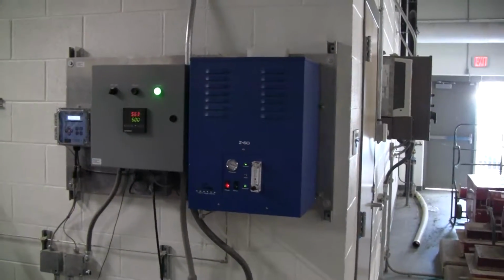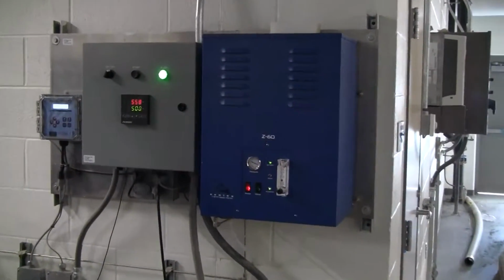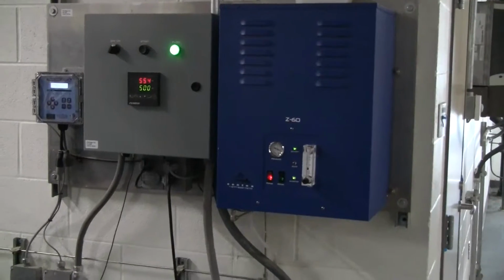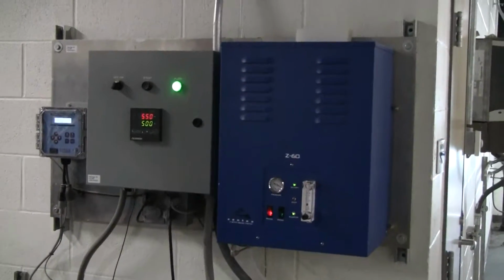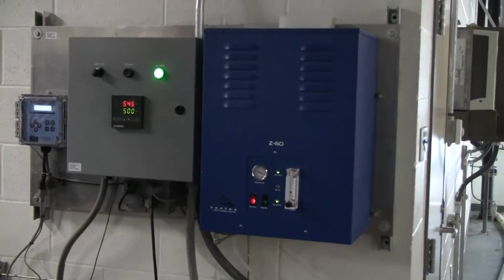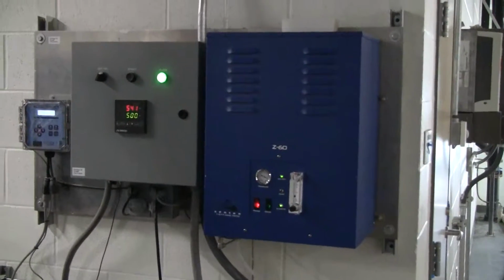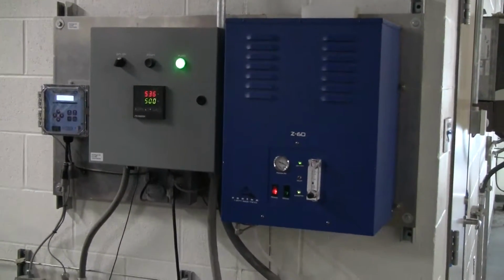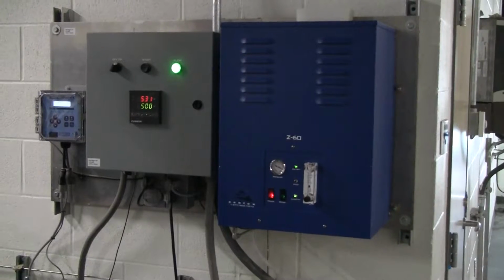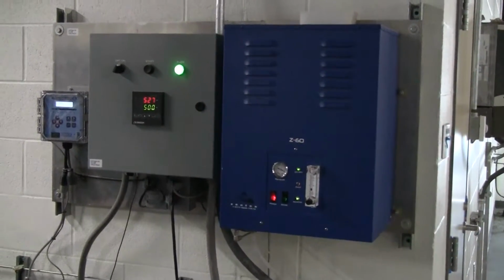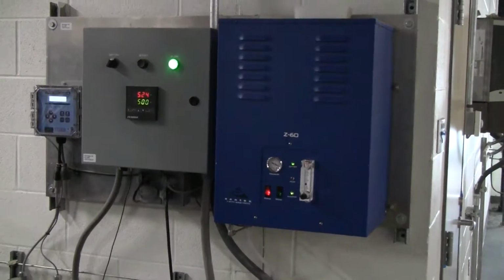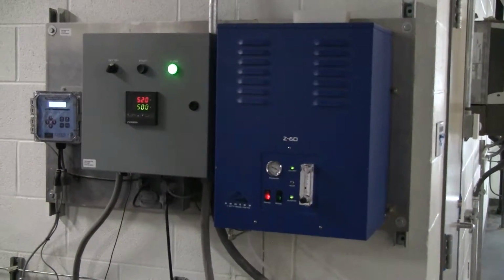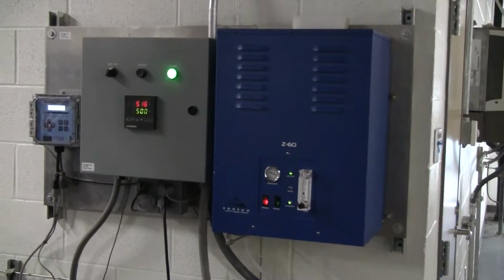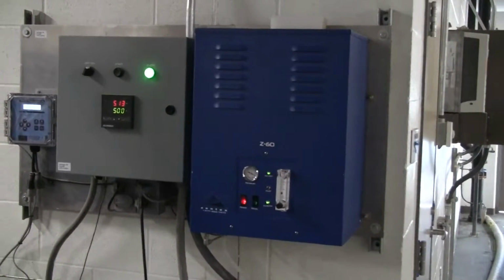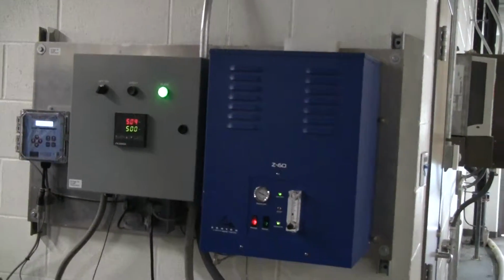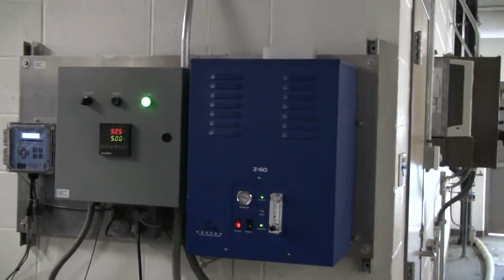The ozone generator basically consists of a plasma block generator where we have plates where we're passing the gas through, and we're controlling the electricity between the plates. As the system's calling for more ozone, we run more electricity through the plates, generating more ozone. As we need less ozone, then we reduce the amount of ozone being made. This is all controlled by the controller here, which is directed by the ORP probe.